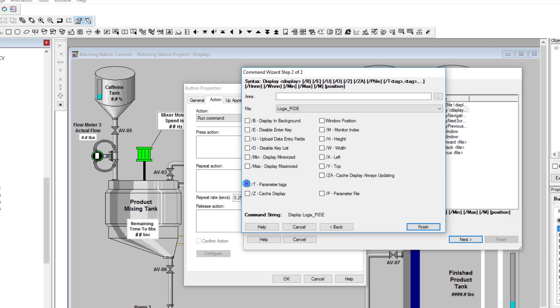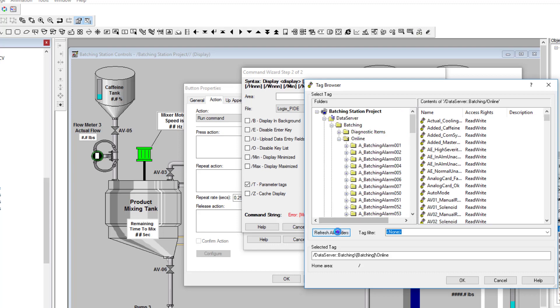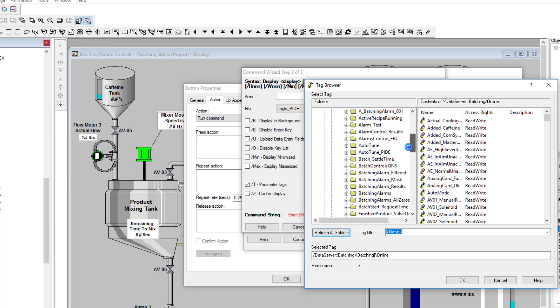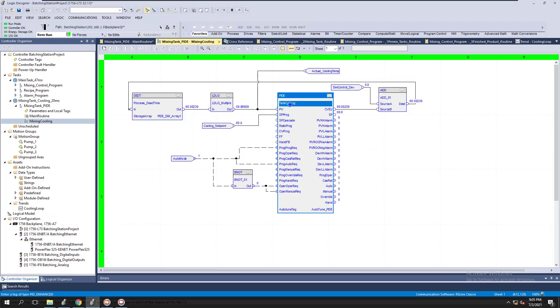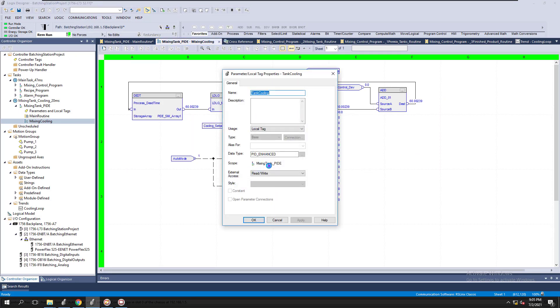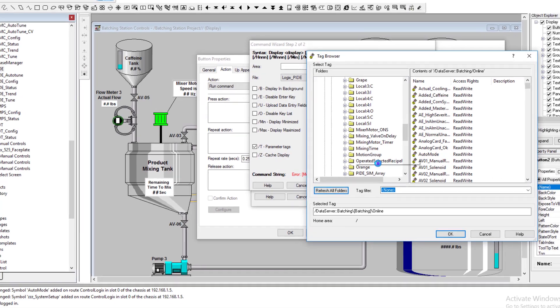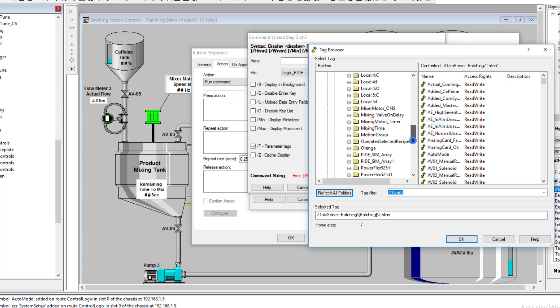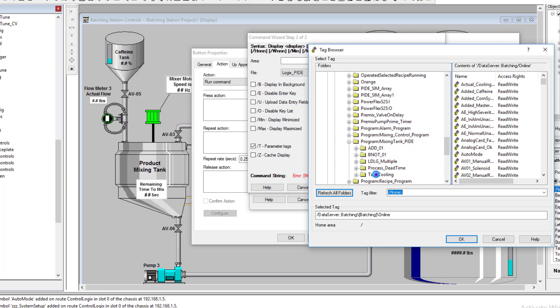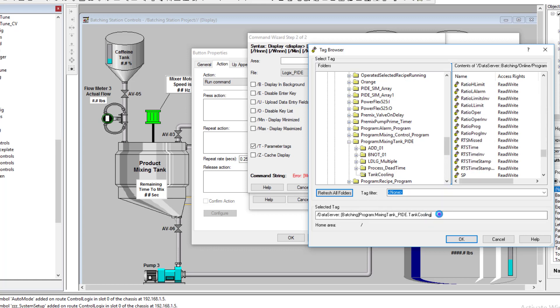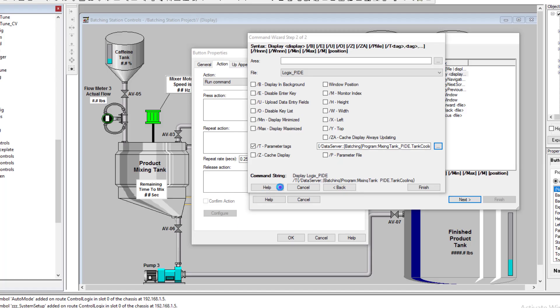Okay, and then we're going to go to parameter pass. This is where we're going to pick our parameter and we're going to come in here and refresh our tag database or refresh our folders anyway. And then we're going to come in here to our program. So we need to make sure that if we go into our program, what program level we put this at and I believe we put it at mixing tank PIDE. So we'll go mixing tank. So this would be mixing tank PIDE. So this would be right here, mixing tank PIDE and this is called cooling and that's going to be the actual PID loop. So tank cooling will be our PID loop that we need and that should be it, right? So this would be the exact thing we need to pull up. So that pulls that up and let's hit finish.